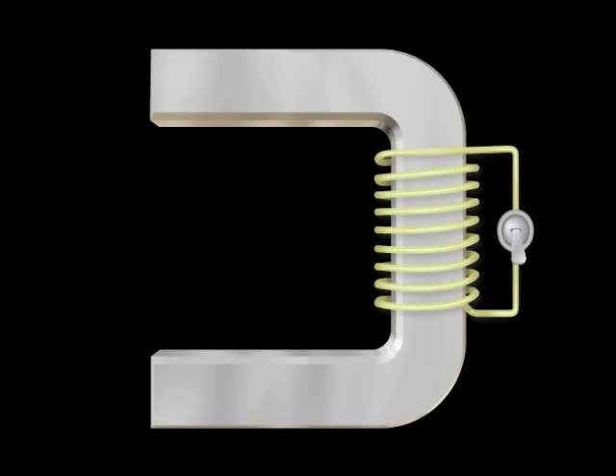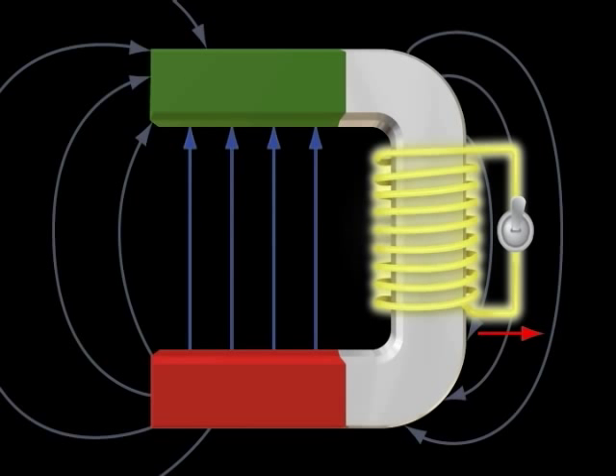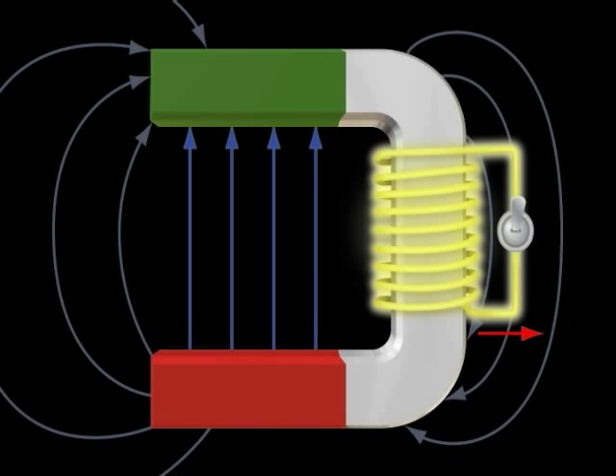With resistive magnets, the field is generated by a constant, external current supply. The current flows through wire coils and generates a large amount of heat in addition to the magnetic field. This heat is drawn off by a water cooling system. Resistive magnets only generate low field strengths, since they are limited by the ability of the cooling water to dissipate heat. In case of an emergency, a resistive magnet can be switched off at any time.